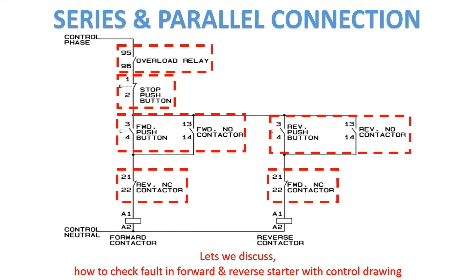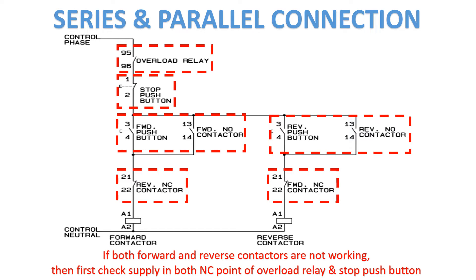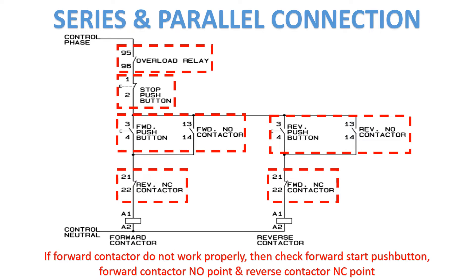Now let's discuss how to check faults in the forward and reverse starter using the control drawing. If both forward and reverse contactors are not working, first check the supply at both NC points of the overload relay and stop push button. If the forward contactor does not work properly, check the forward start push button, forward contactor NO point, and reverse contactor NC point.